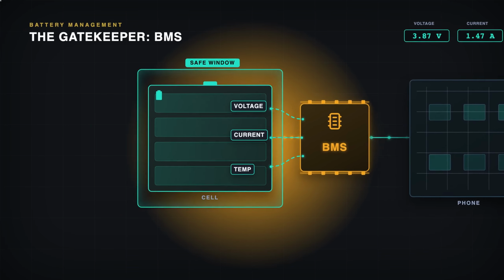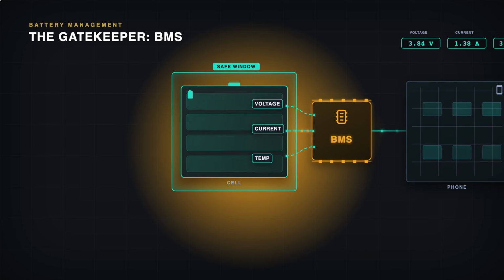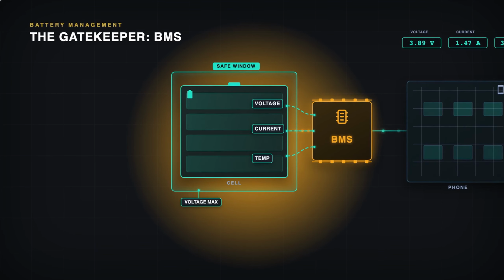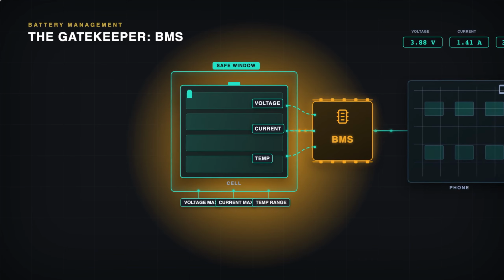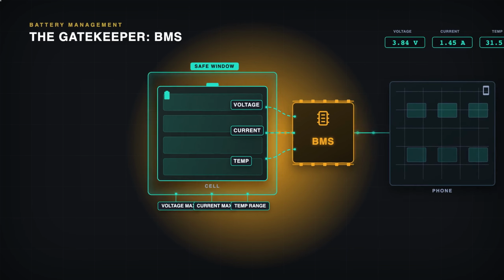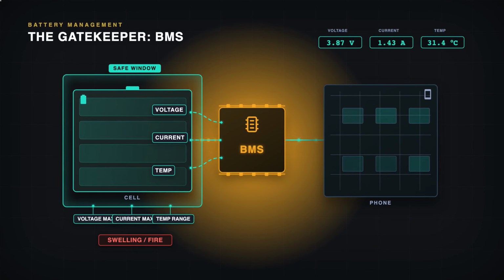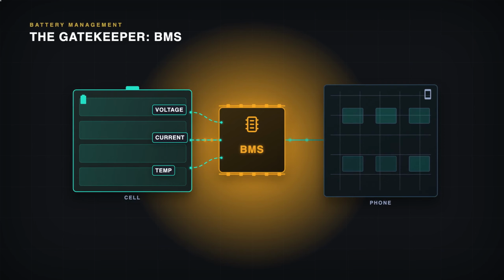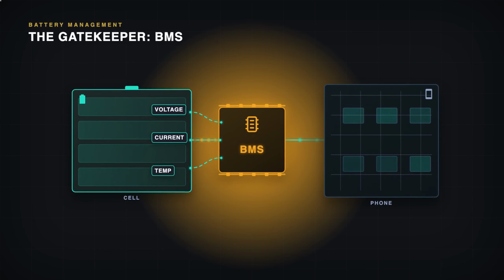From those readings, it enforces one core idea: the safe operating window. That's a set of bounds the cell must stay inside. A voltage it can't rise above, a temperature range it can't leave, a current it can't exceed. Inside the window, the chemistry is calm and predictable. Step outside any edge, and the cell starts down the road to swelling or fire. The BMS is the enforcer of all 3 of those rules at once.